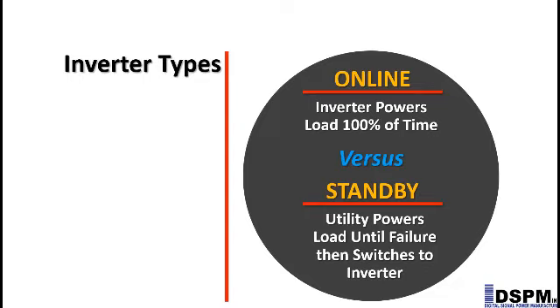In contrast, our standby inverters are at the ready in the event the utility power fails, at which time DSPM's inverter switches the power load to the battery array. Your only question is, which one is right for the application? Your decision depends on the type of load you wish to protect. If you need backup power for fluorescent lights, our standby inverters will likely do the job. However, if you need clean, uninterrupted power for your computer systems, critical medical equipment, or other power-sensitive systems, then you need to employ one of our online inverters.